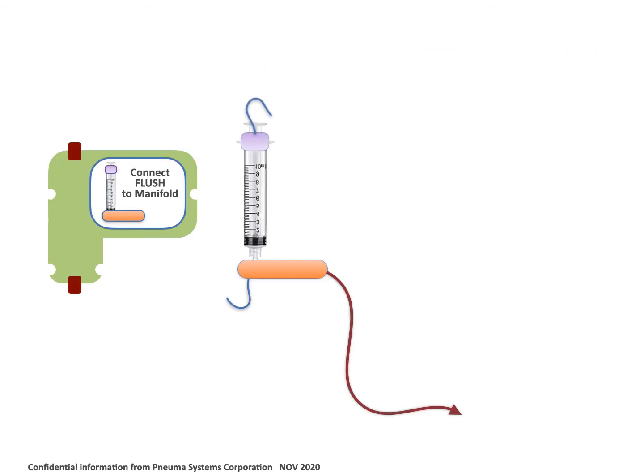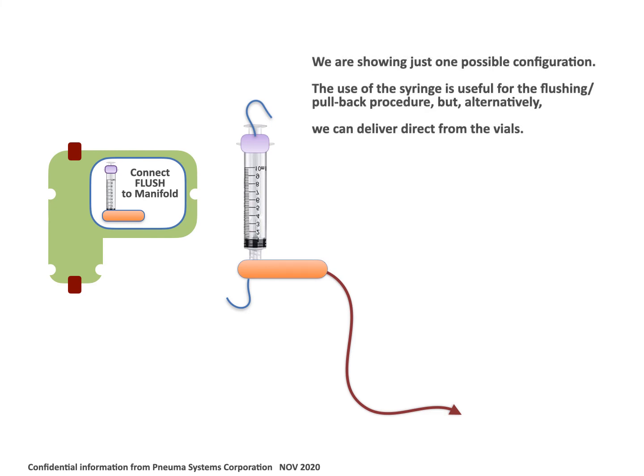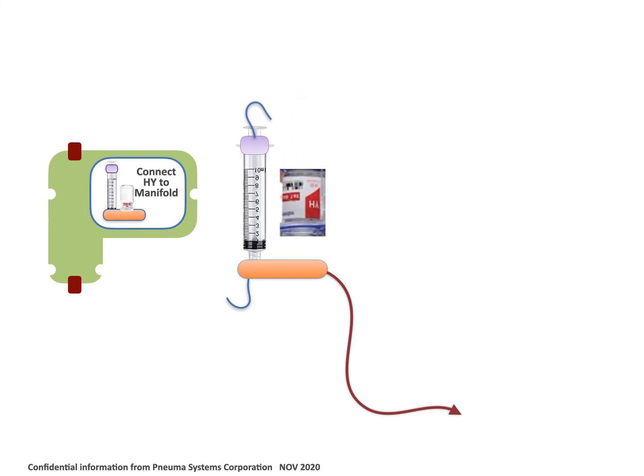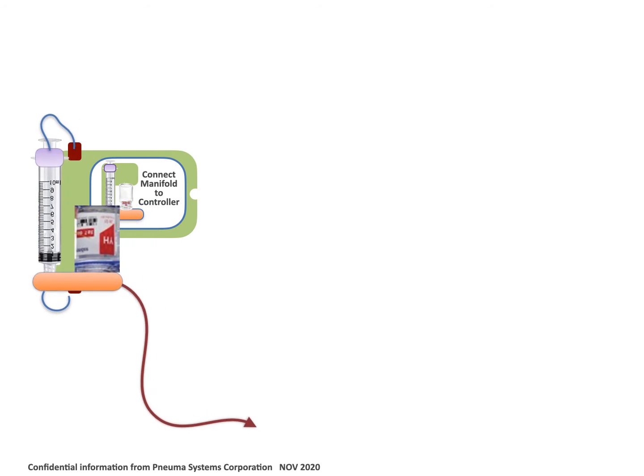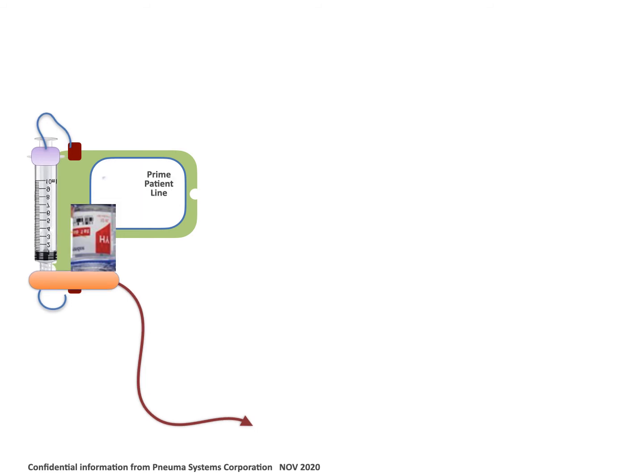For immunoglobulin, here's a configuration where we have a manifold that's got a pneumatic connection. We're showing a flush syringe being connected to a disposable manifold. We then connect hyaluronidase as an example in this application. We connect the manifold to the device through a pneumatic connection. The line is primed using the pre-filled saline flush syringe.